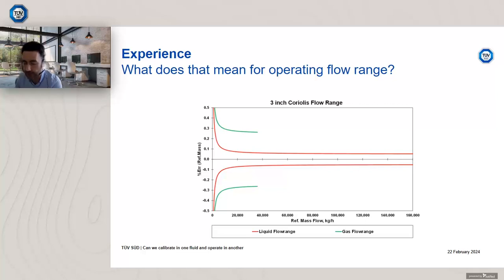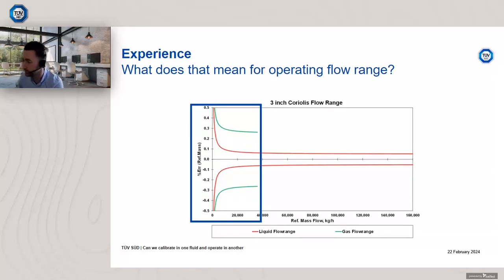Now, the first obvious question is, if you're using it in gas, what range should you calibrate it for liquid? If you're using it in gas, you're only using it in this very small range. Should you then calibrate in liquid flow in this very small range? Now that's a very small part of the turndown of a Coriolis meter.